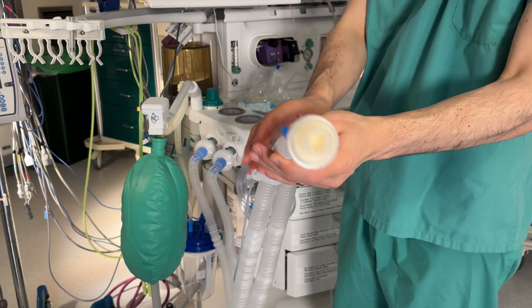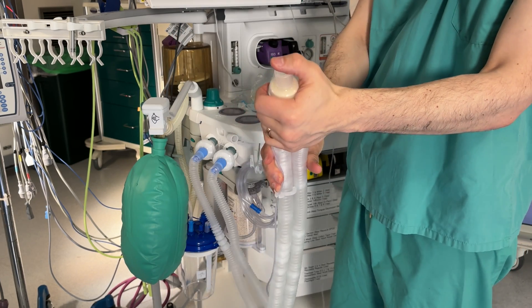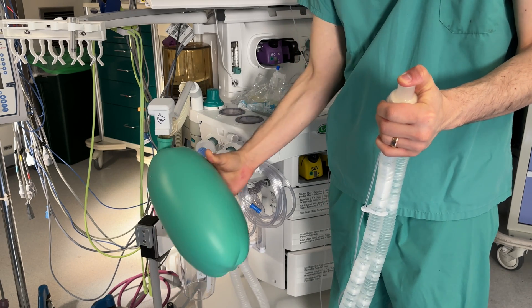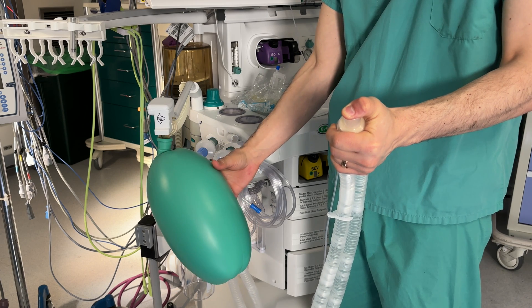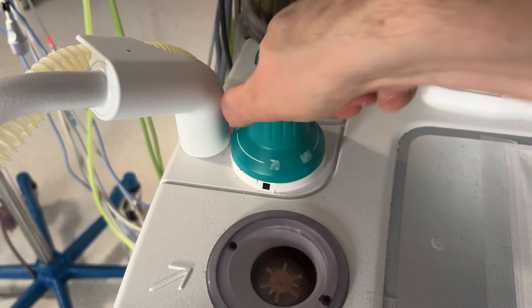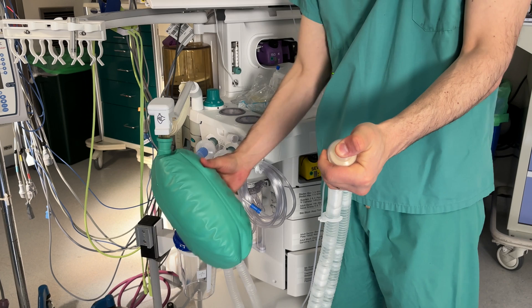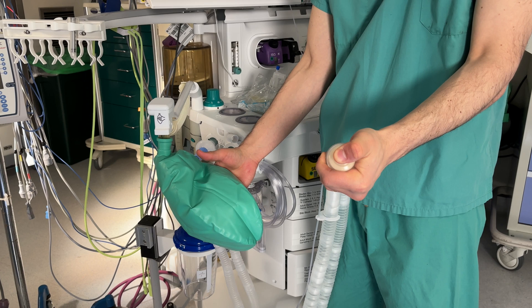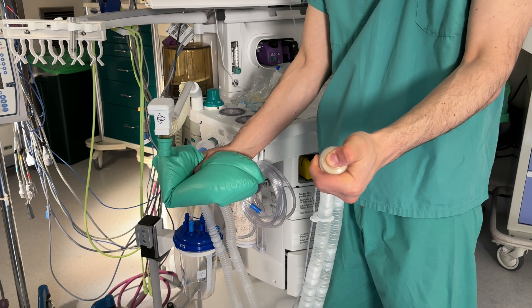With 10 liters per minute of oxygen flowing through the circuit, when I put my thumb on the circuit and occlude it, you can appreciate that this bag, which is connected to the APL valve, gets quite tight. The maximum pressure inside the circuit is 70 centimeters of water, which is what I dialed into the APL valve. Now if I open the APL valve by turning it all the way down to its minimal setting and then attempt to occlude the circuit again with my thumb, you can see that the bag doesn't really inflate very much because not much pressure is allowed to build up in it — the excess pressure is released by the APL valve.